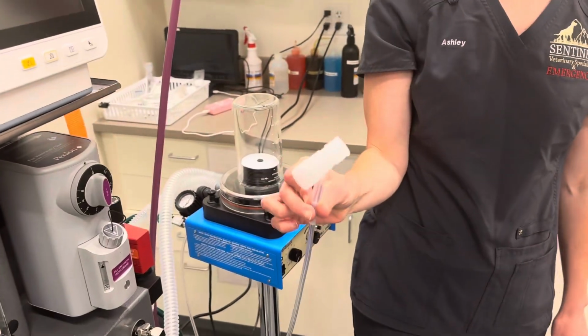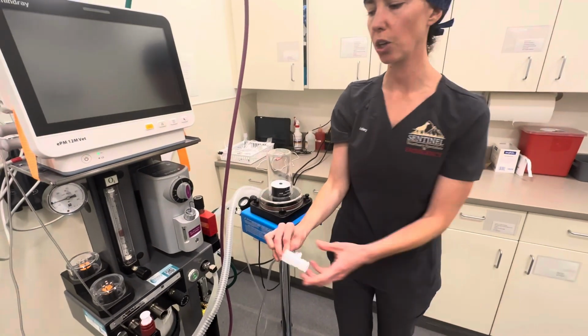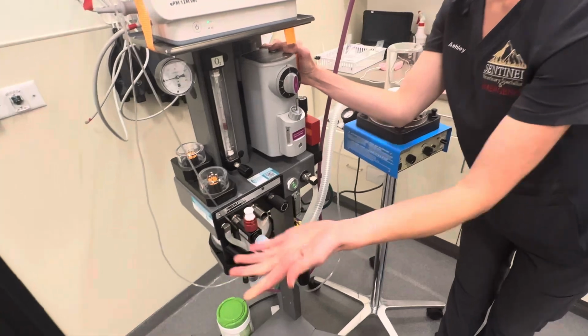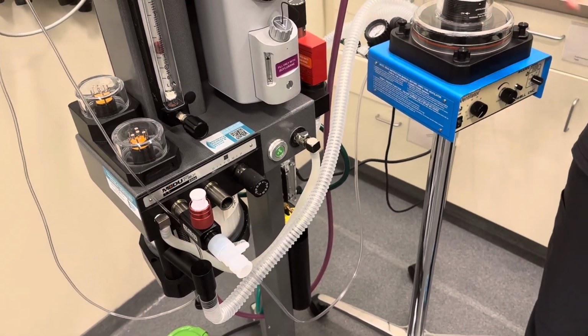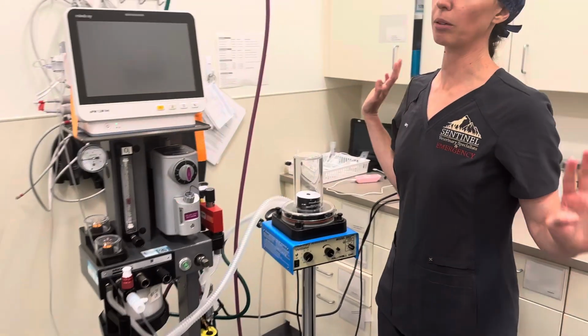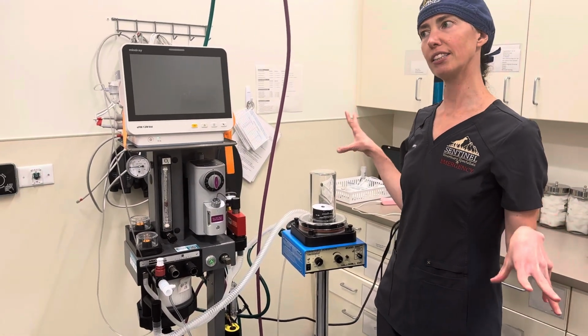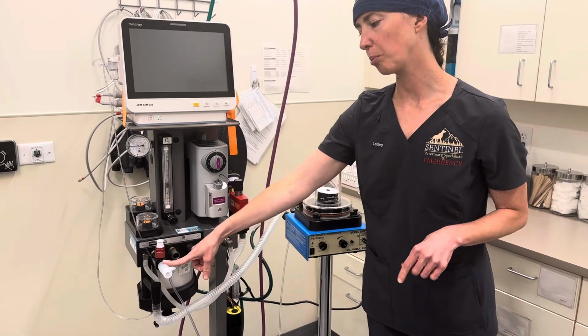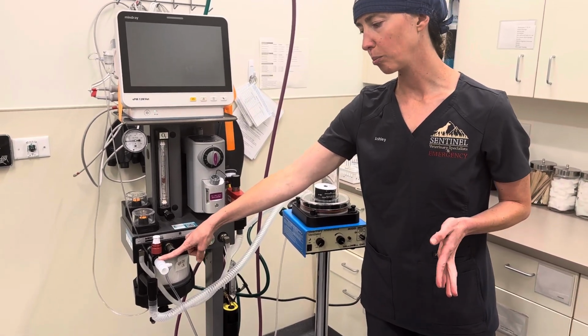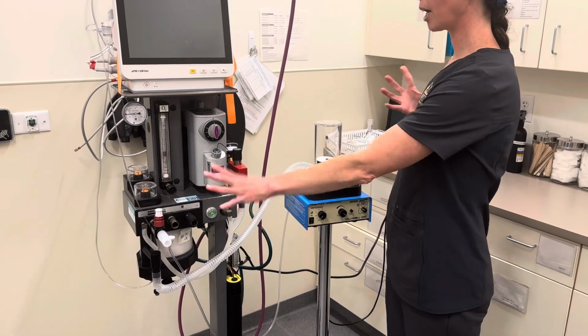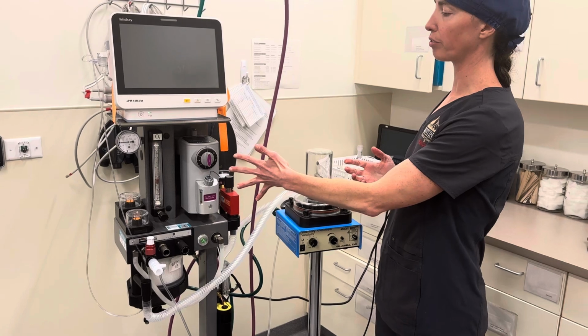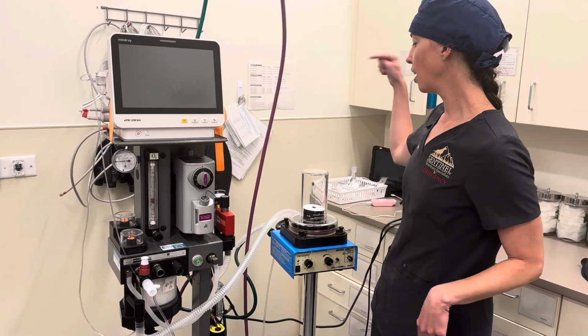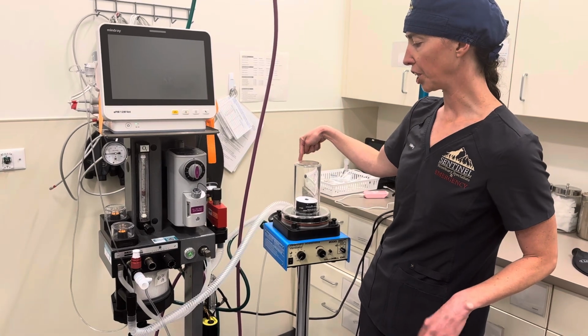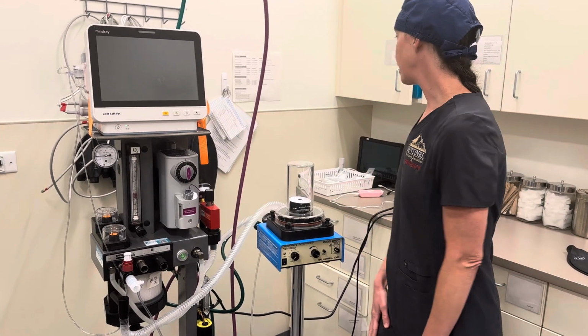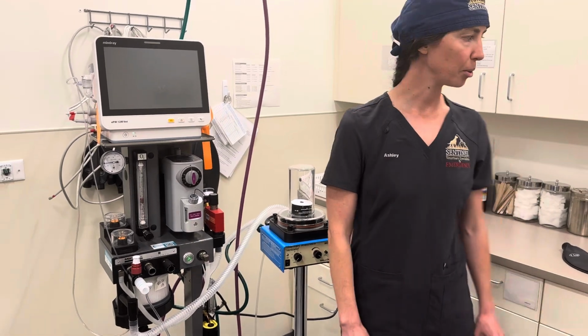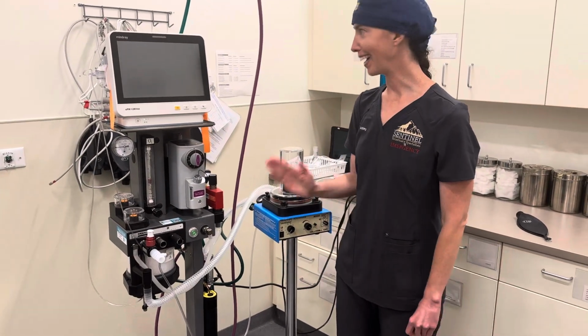But this piece of tubing is really important, and if you don't have this tubing hooked up to your inspiratory limb, it can also be on the expiratory limb, but it has to be on one of them. When you turn the machine on, it will just alarm, alarm, alarm, and it will drive you absolutely crazy, and you'll be like, why is this alarming at me? Probably because you don't have your pressure reader on the inspiratory limb of the machine. So we've got that set up, we've got our pop-off valve closed, we have our oxygen flow on, we'll have them on whatever percent isoflurane. We have our scavenge on the back of the machine hooked up to our active scavenging unit. And now I need to get rebreathing hoses for right here, which I didn't grab.